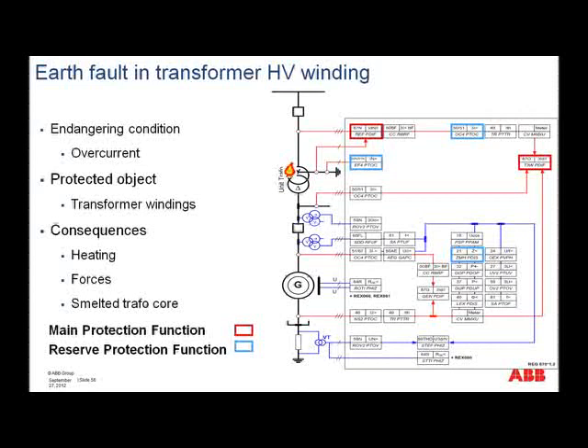All right, if we look then at earth fault in the transformer HV winding, here of course, if it's on the star winding, we have the 87N, or the restricted earth fault, as the main protection. As reserve protections would be the earth fault or ground current measurement in the star point. We have also the under impedance function, and we have the phase overcurrent function, should the current in the faulted phase, fed from the network, be such that it can be detected by this overcurrent protection.